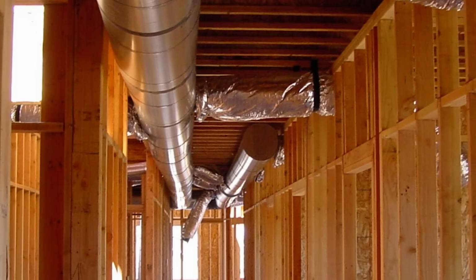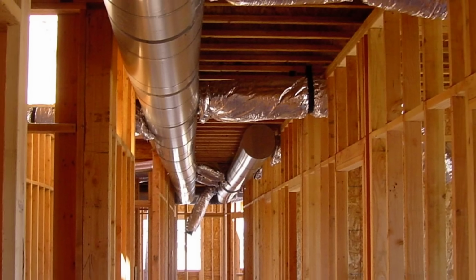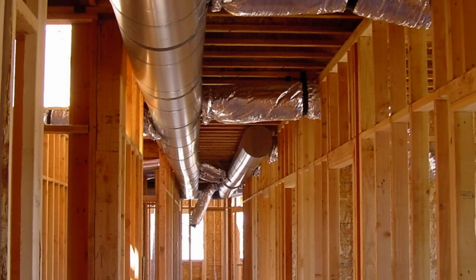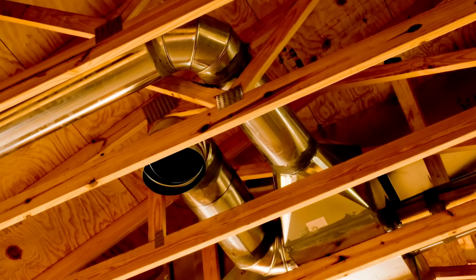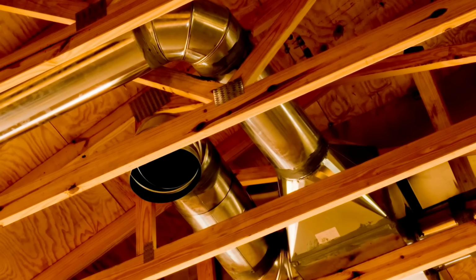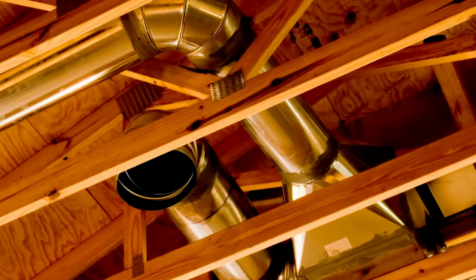Number 2, this one I see broken maybe every single day: technicians, when installing the heating and air system, just install a box and don't care about the ductwork. They don't care about airflow, they don't look at duct sizing. They don't say, if I'm installing this new system, I need to look at everything in place and make sure it's all installed properly, that I've got good static pressures and so on.